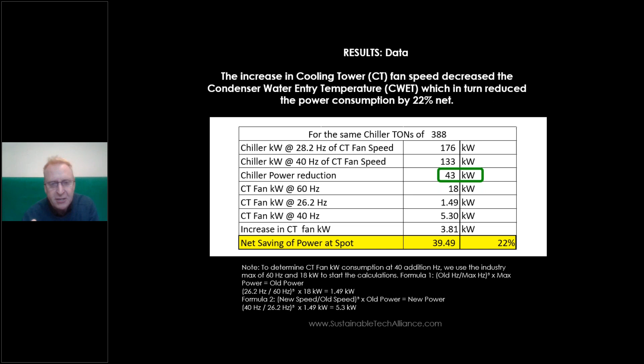And the way that we have to demonstrate the savings is through multiple paths. It's either the International Performance Measurement and Verification Protocol, IPMVP, which has certain standards. In some cases, facilities have recent BMS systems, typically in the last 10 years, that are already capturing data, the amperage data to the hour. We can convert that to kW based on voltage. And in many cases, they also are archiving a trailing year or two of data. That sets an excellent benchmark. If we don't have those options, the facility managers can turn OptiKW off and on, just as a pilot can do so with autopilot. And they can see within the same month the actual savings.